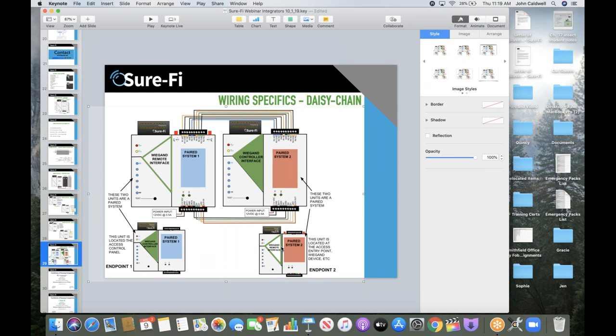One question from Brian Lux: what will be a typical data rate over the radio, RS-232, RS-485 in perspective? In its fastest setting, about 8,000 bits per second is the most it can do, and that's with the radio's settings set up so that it moves the fastest amount of data. Usually, when we do a command or an event-based bit of information, it's not necessary to go that fast, but it depends on what's happening, if it's a polling system or event-driven or whatever.